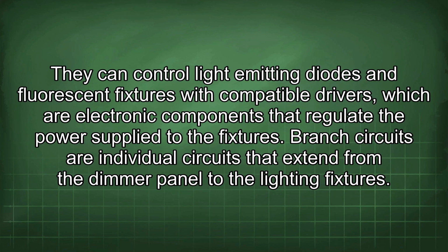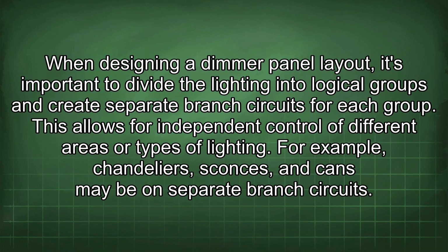to the fixtures. Branch circuits are individual circuits that extend from the dimmer panel to the lighting fixtures. When designing a dimmer panel layout, it's important to divide the lighting into logical groups and create separate branch circuits for each group. This allows for independent control of different areas or types of lighting. For example, chandeliers, sconces, and cans may be on separate branch circuits.